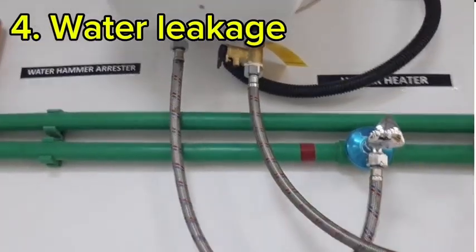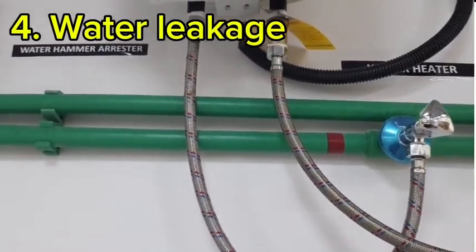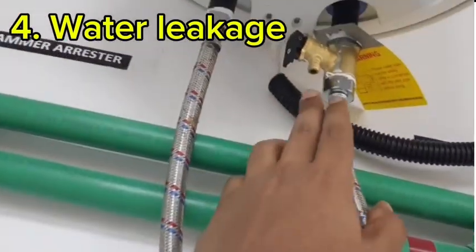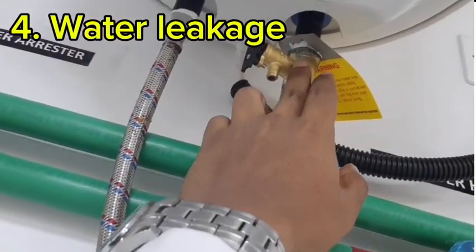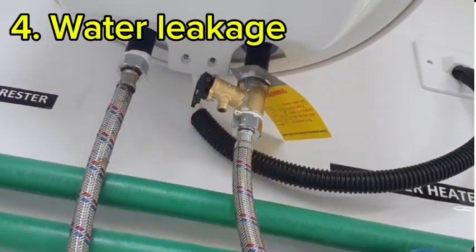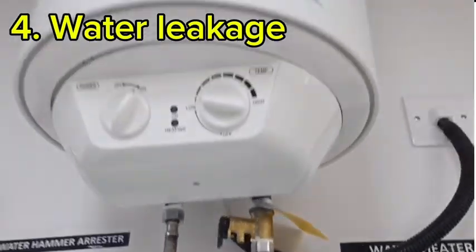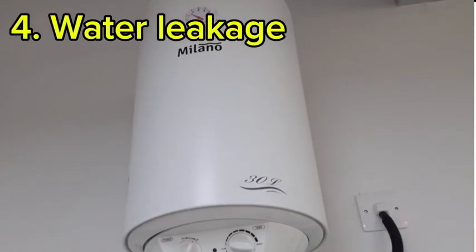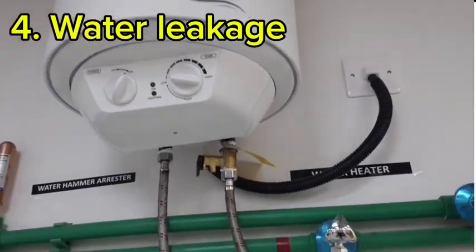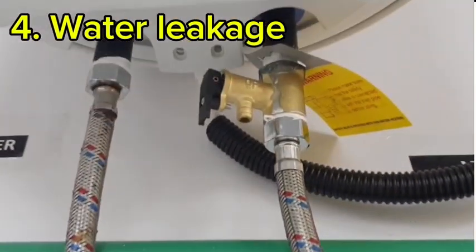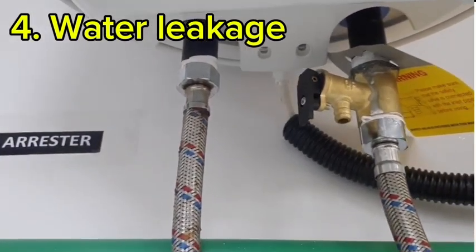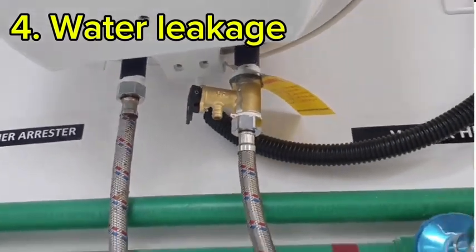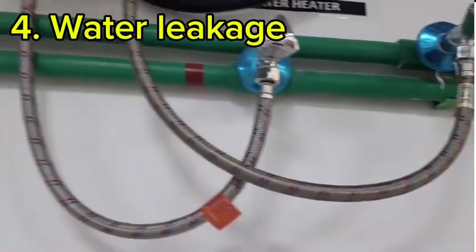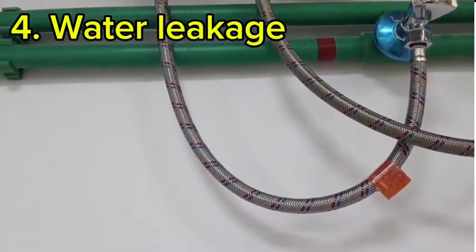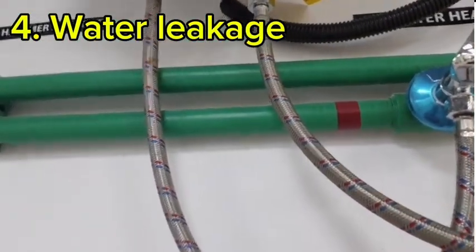If you get a complaint for water leakage, what do you need to check? First of all, you have to check the relief valve. You can see the relief valve, if it is bad, then there will be water leakage. Second, physically check the tank condition. If there is any physical damage in the tank, there will be water leakage. Then check the pipe joint condition. You can see where our hose pipe is connected. You have to check all the joints. Then check the hose pipe condition. Due to a very old hose pipe, you may get a water leakage complaint.